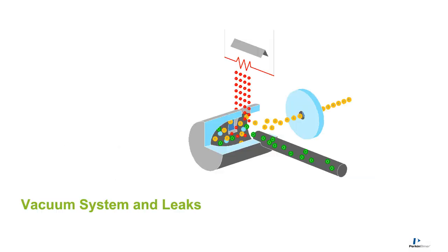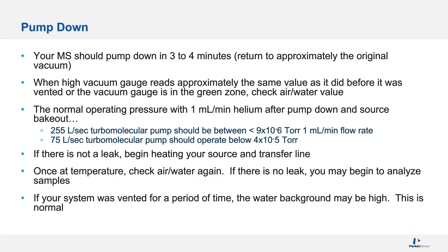Okay, let's move into the vacuum system and we'll talk about leak checking. I don't know why I did pumping down before venting. Pumping down, your mass spec should pump down in 3 to 4 minutes, which means it's returning to its original vacuum before it was vented.